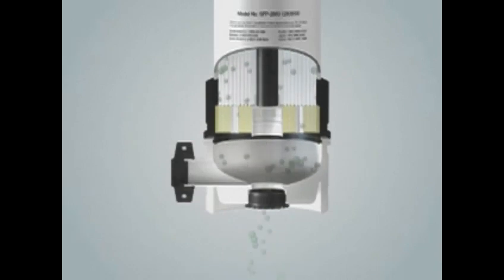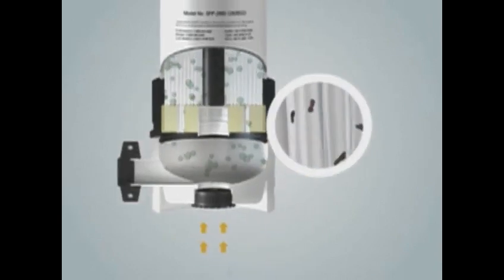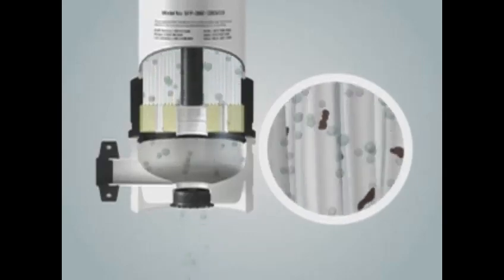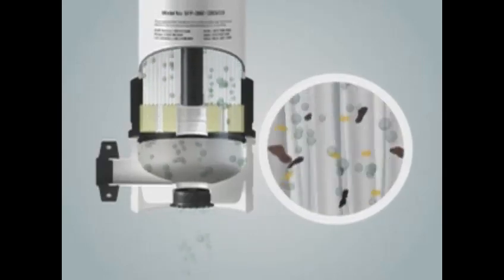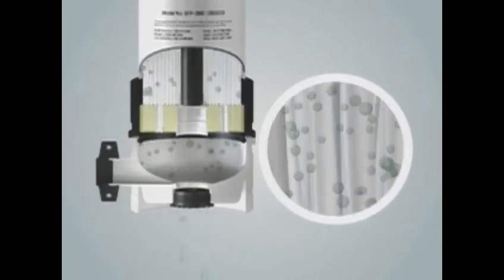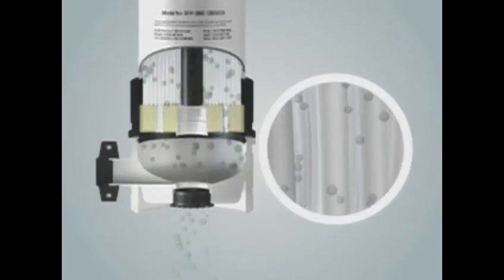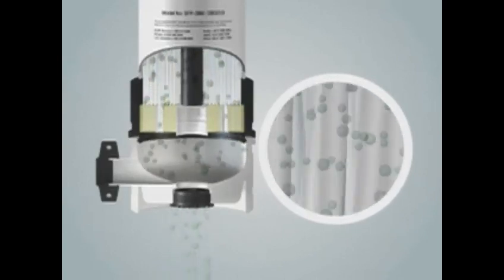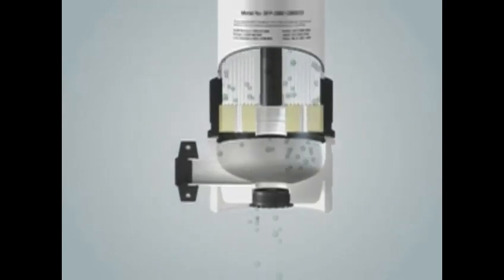As air is introduced at low pressure into the feed side of the module, air travels up the outside surface of the fibers, causing vigorous movement. The shearing effect of the airflow loosens particulates attached to the fiber skin. While backwash reduces fouling due to pore blockage, air scouring acts to free particulate deposits from the fiber skin and thus greatly improves cleaning efficiency.